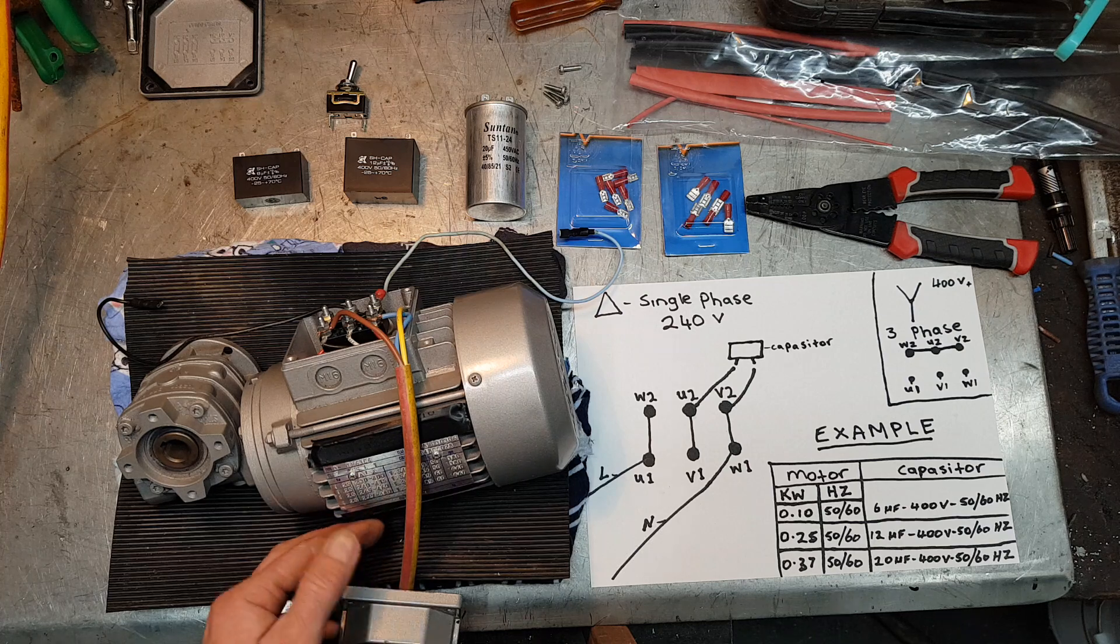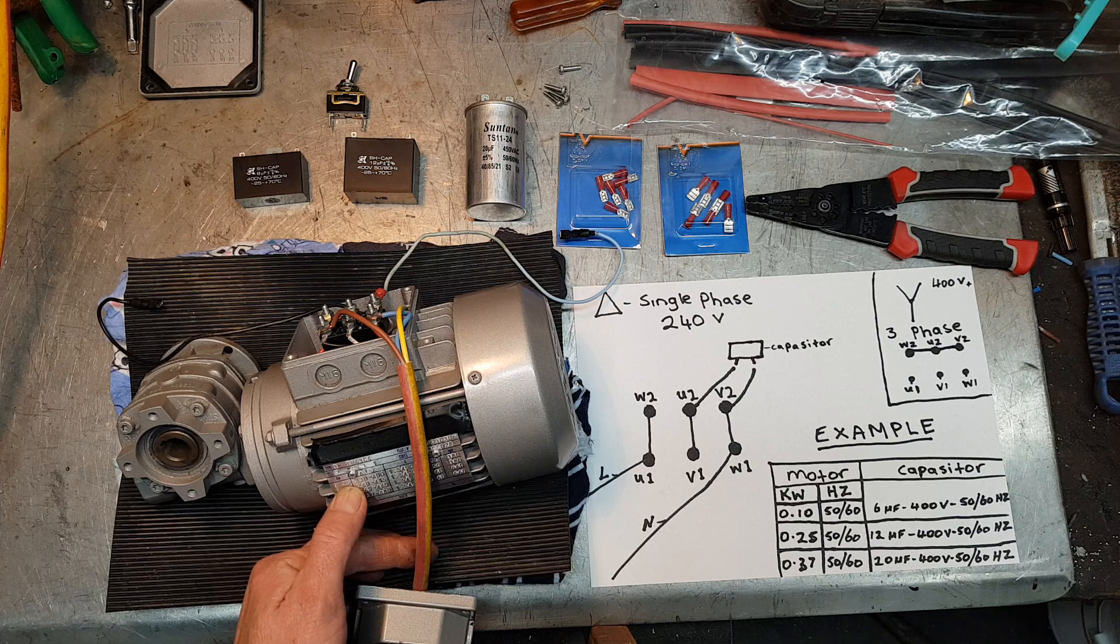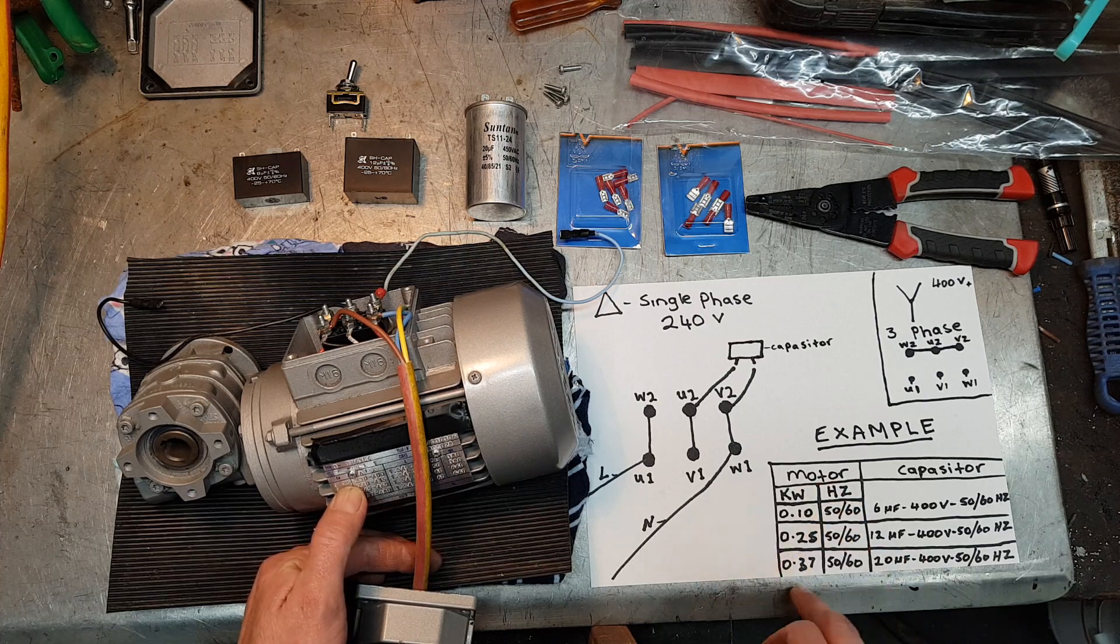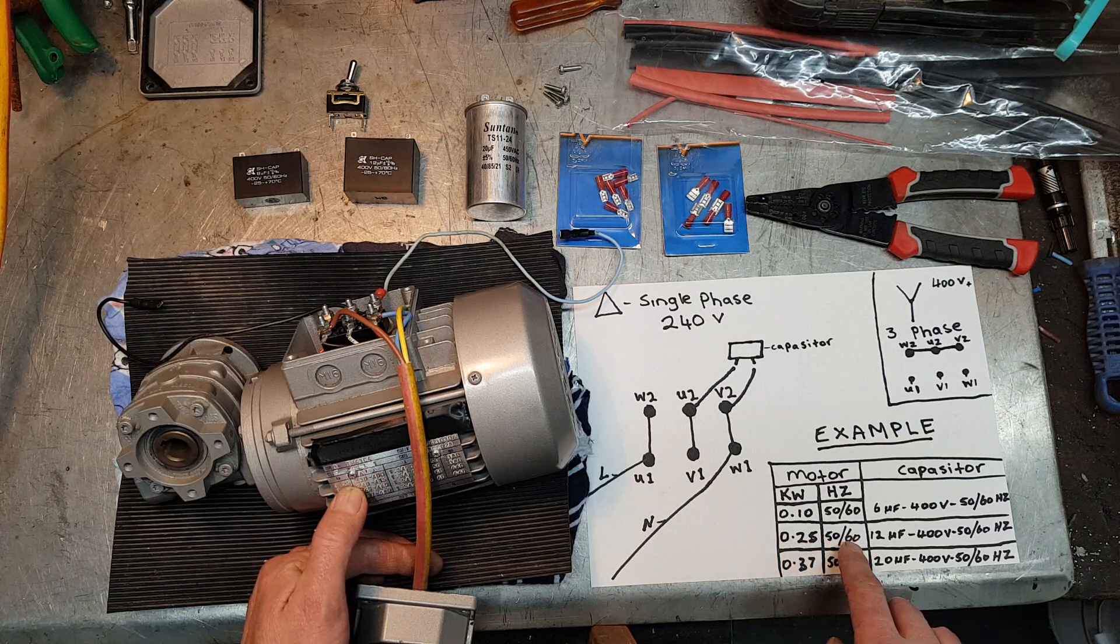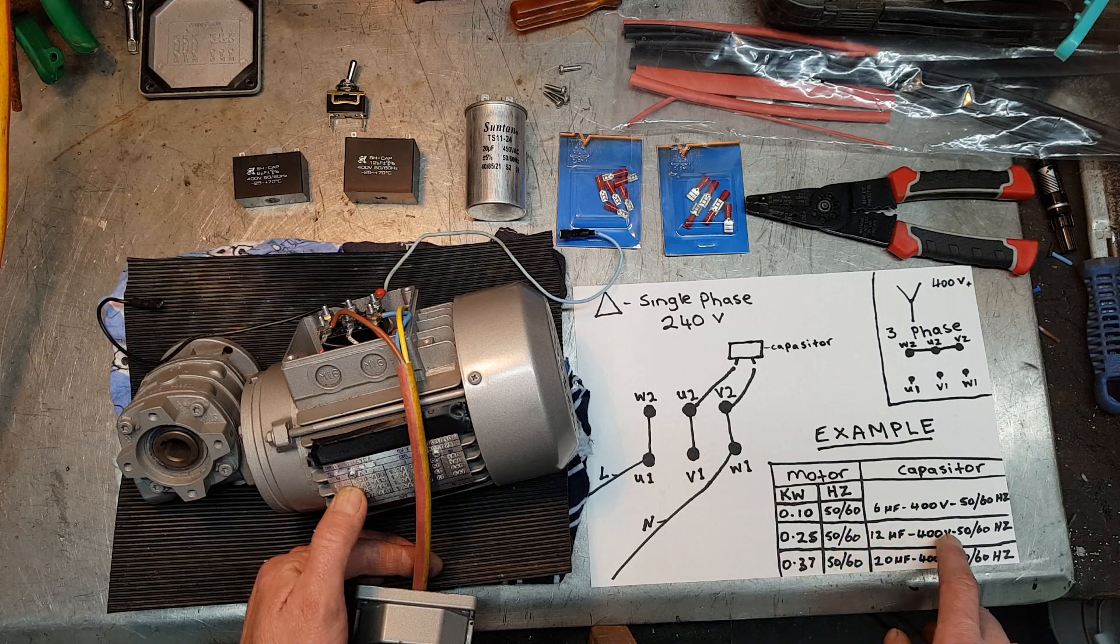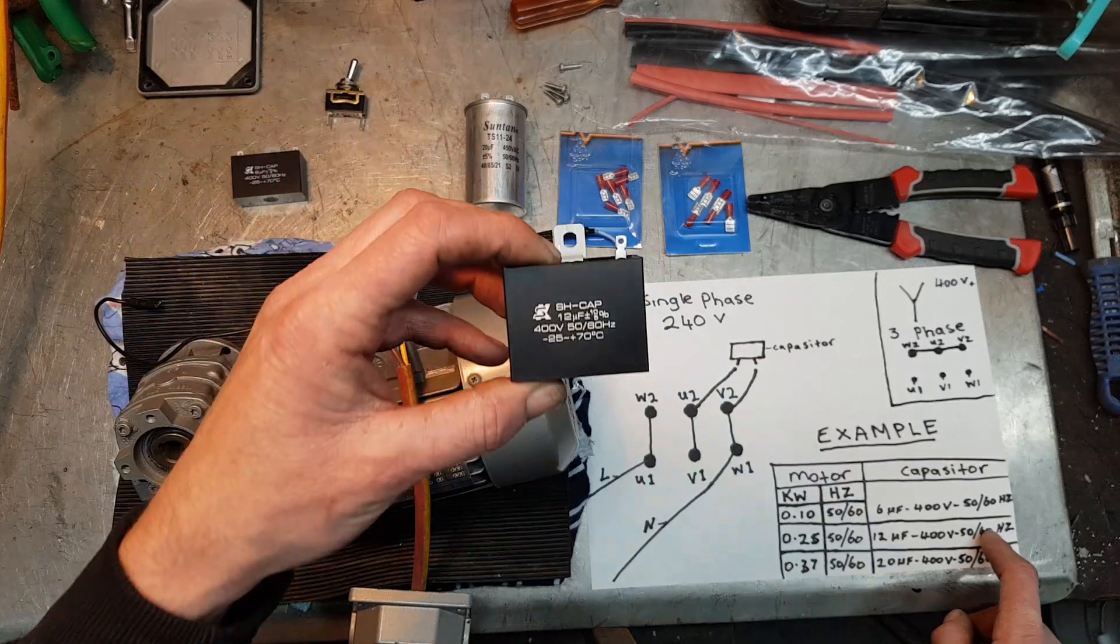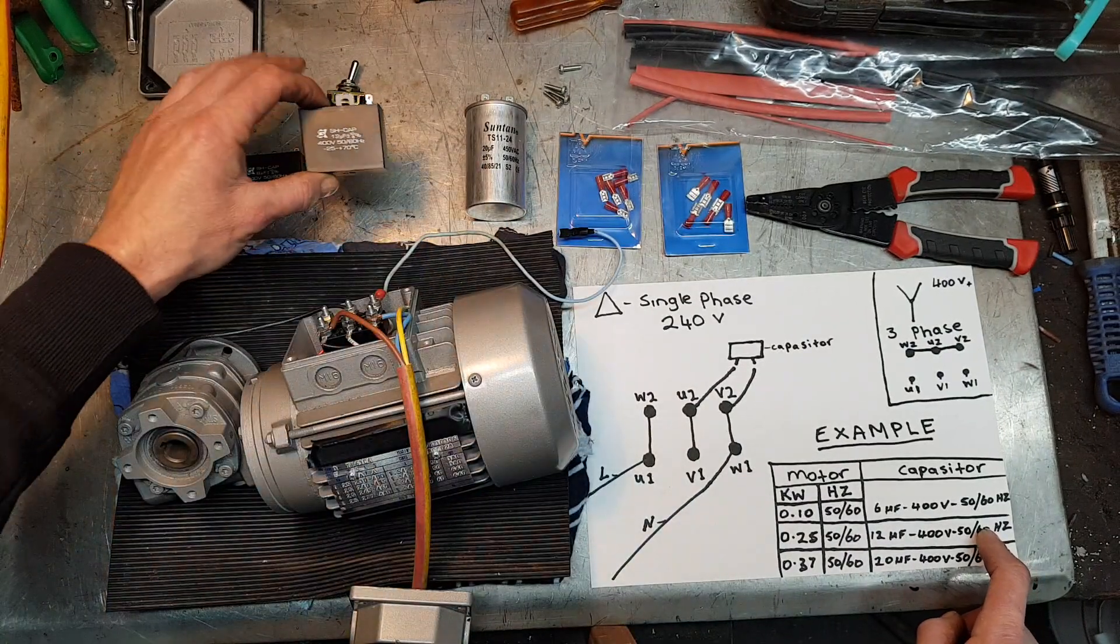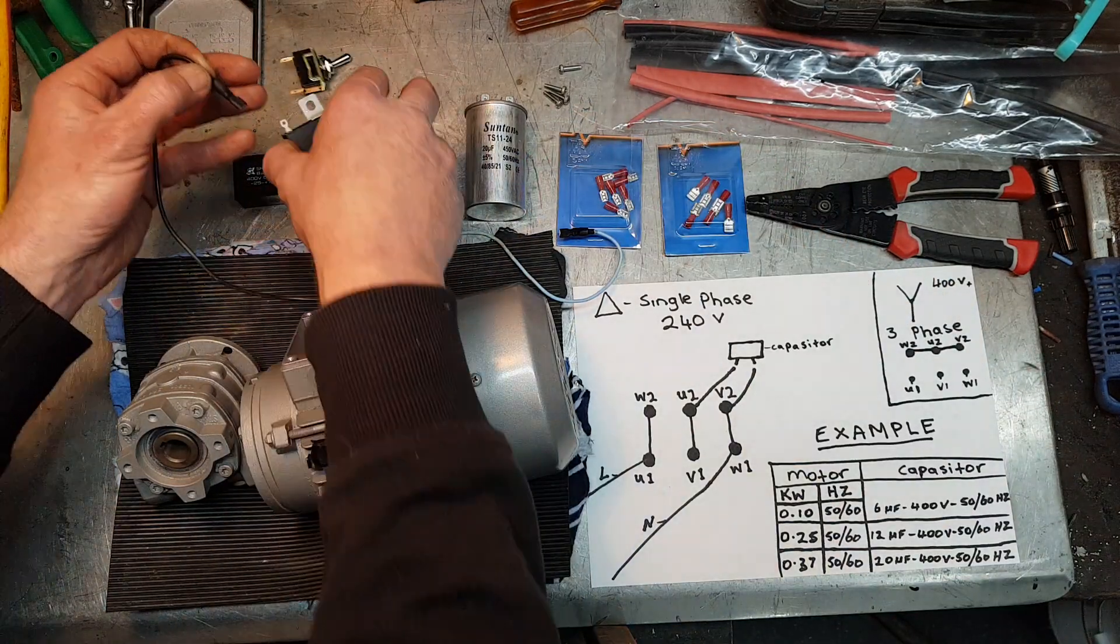So this motor is a 0.25 kilowatts, 50 or 60 Hertz. I've worked out, I've done a couple of different motors. At the moment we're doing this one, 0.25 kilowatts, 50 or 60 Hertz, so I'm going to use a 12 uF, 400 volt, 50-60 Hertz capacitor, which is this one right here. Get these from most electrical shops. So I'll go ahead and plug this up.